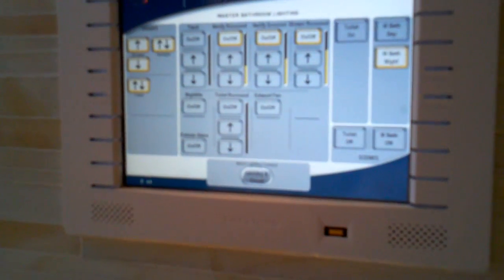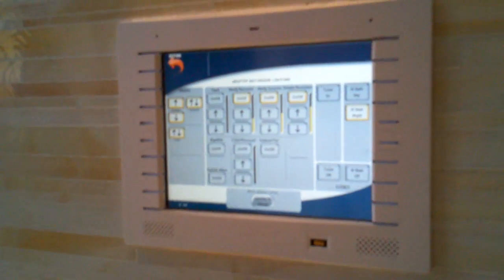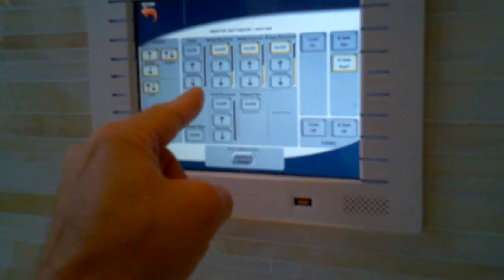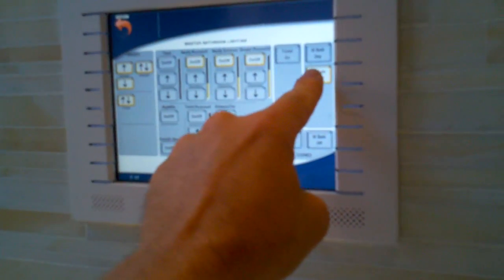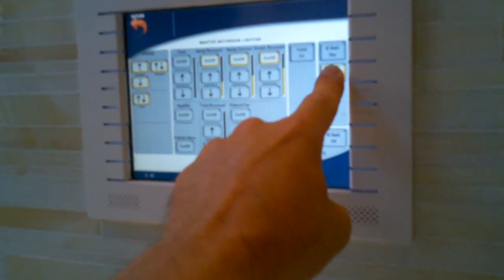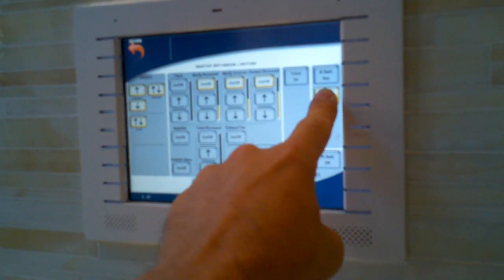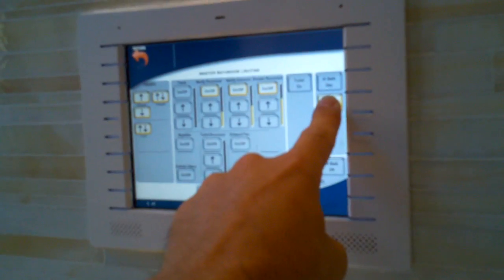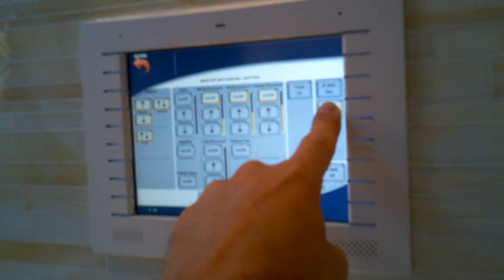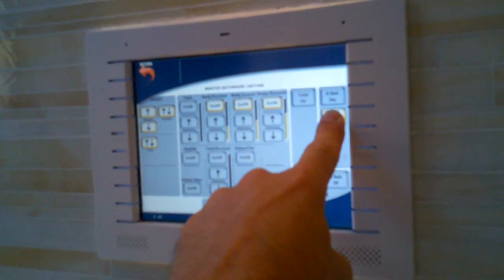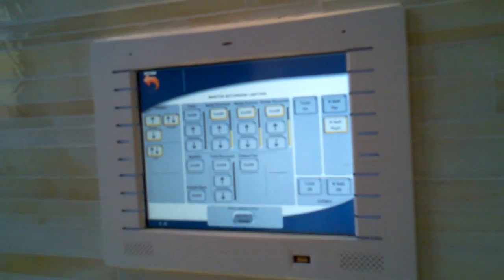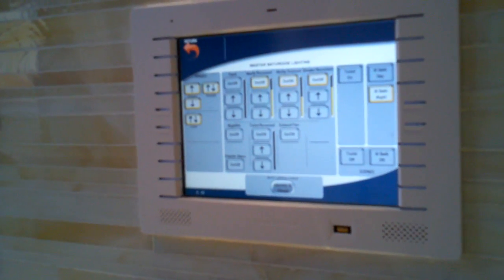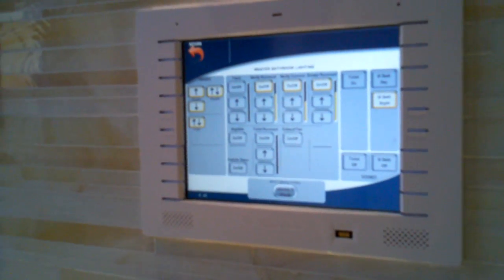If I don't like that level, or say somebody else in the house doesn't like it, and in this case, we know the customer might not like it, instead of trying to figure out how the client had it before, all I'm going to do is press and hold this button. But instead of holding it for 5 seconds, I'm going to hold it for 15. It's going to do its pulse thing again, and it will re-engage the originally programmed preset. And there it is. And that is it for lighting control in a bathroom.